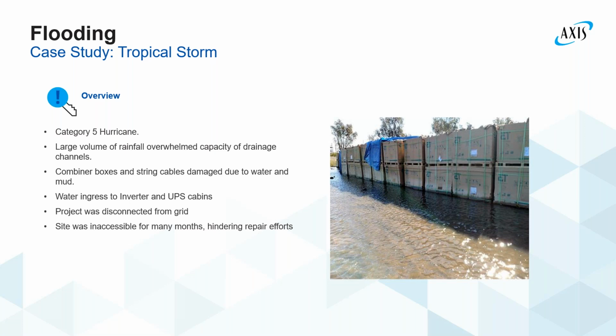So if you haven't got backup power, if you haven't got enough diesel generators, if you haven't got big enough UPS batteries, you're playing this cat and mouse game, hoping the grid comes back on so you can keep your auxiliary power running. If that doesn't happen, you run out of diesel, you run out of battery power, the whole site powers down, and you can have a lot of damage done to those inverters and battery components because the air conditioning isn't working. It sounds so straightforward and obvious, but we've seen it on a number of occasions now.